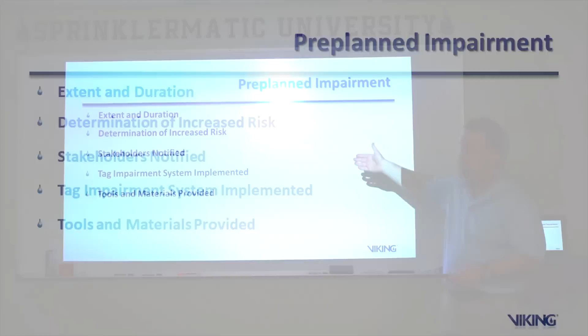In a pre-planned impairment, we have to determine the extent of the risk, extent and duration. How much of the building is going to be affected and for how long? And right after that comes a determination of the increased risk. And this is important because if we shut down a sprinkler system in a given portion of the building that happens to also have some high hazard operations in it, what are we going to do? What's that determination of risk?